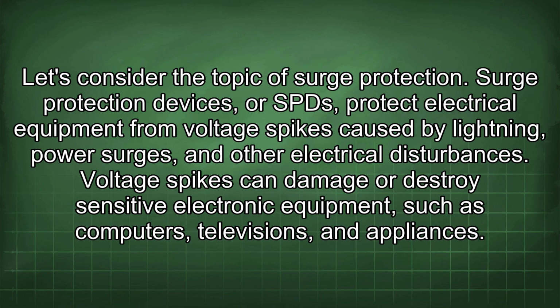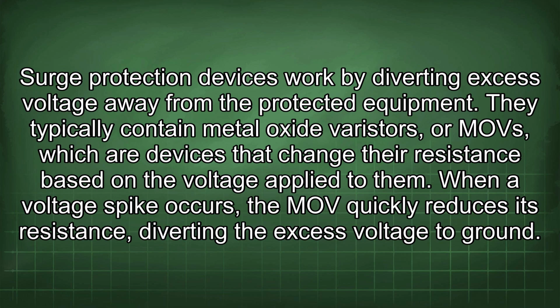Surge protection devices, or SPDs, protect electrical equipment from voltage spikes caused by lightning, power surges, and other electrical disturbances. Voltage spikes can damage or destroy sensitive electronic equipment such as computers, televisions, and appliances. Surge protection devices work by diverting excess voltage away from the protected equipment. They typically contain metal oxide varistors, or MOVs, which are devices that change their resistance based on the voltage applied to them. When a voltage spike occurs, the MOV quickly reduces its resistance, diverting the excess voltage to ground.